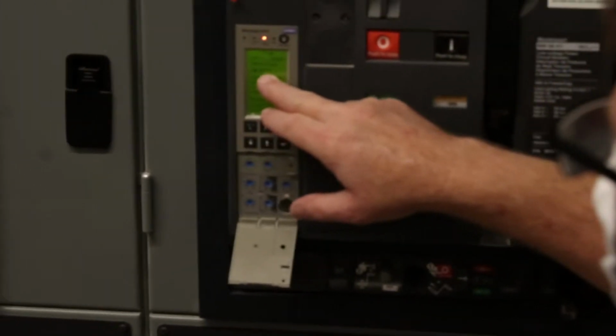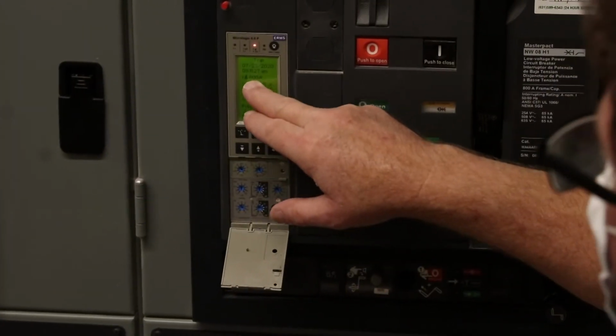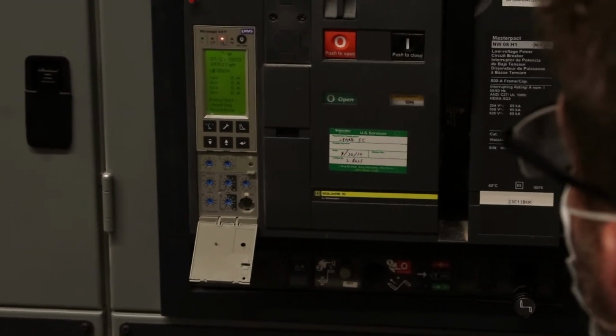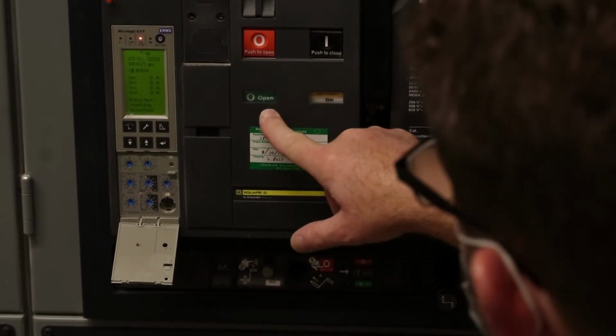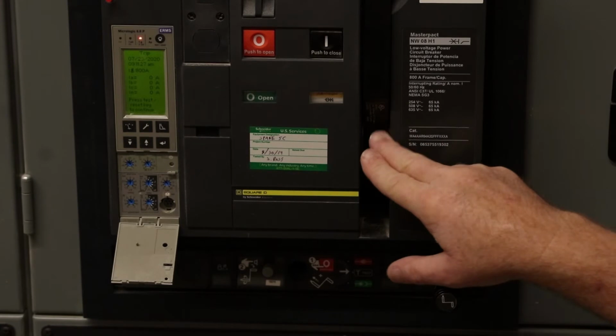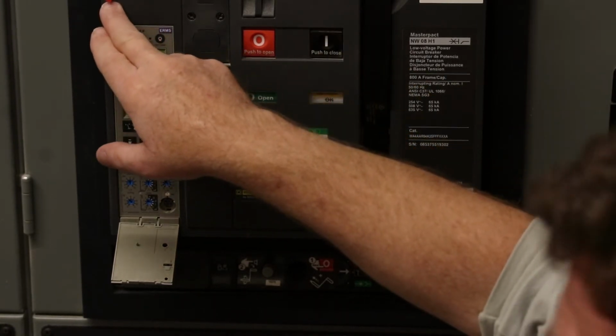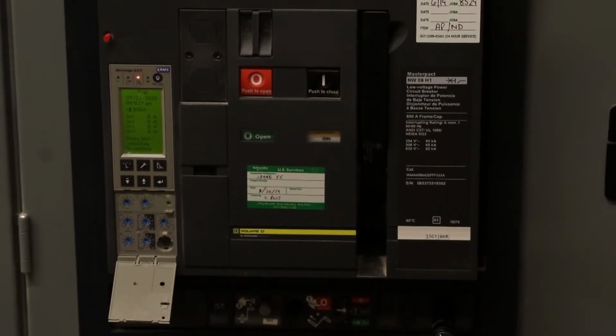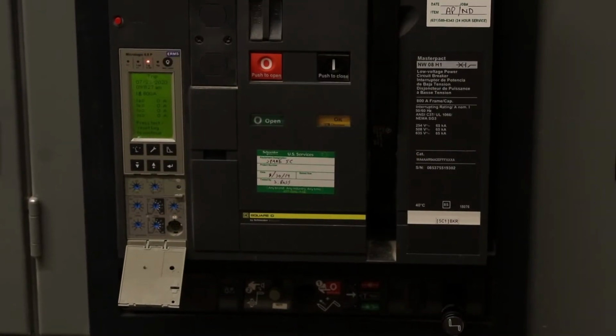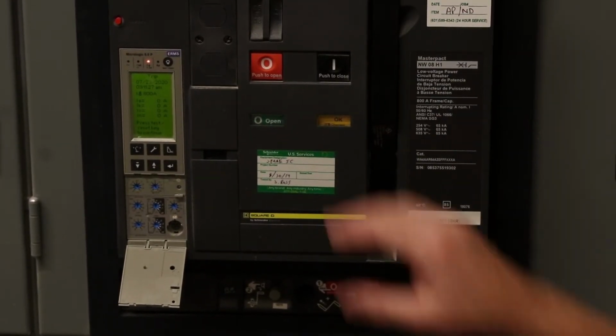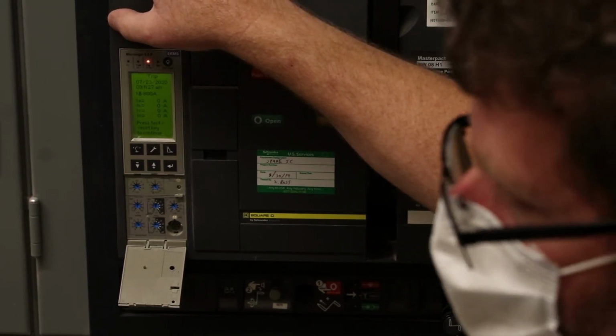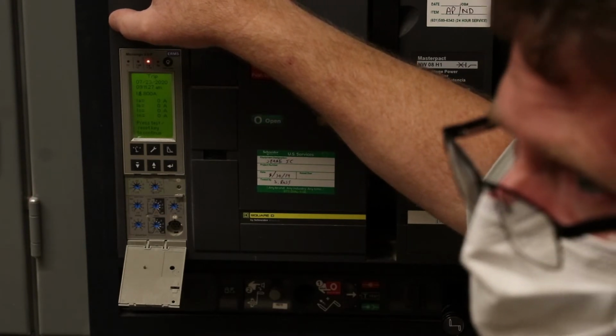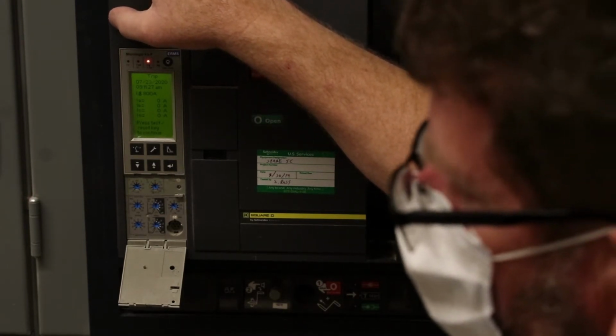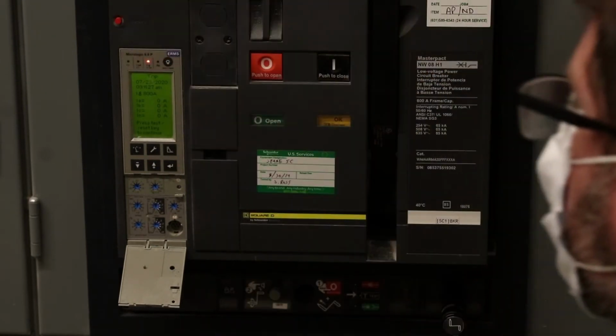Push the test on the ground fault, tripped off on ground fault. It shows you your date time stamp. It's not showing any phase current because there was no phase current. Simulated ground current was 800 amps. Okay, the breaker's open now, but it's still saying charge not okay. Saying charge not okay because it's not okay to close, because your red button's popped out. It's tripped. Resetting this doesn't mean the fault's cleared. Whatever tripped the breaker, that doesn't mean the fault's clear. That's just one step we put in the process to aid the operator to make him think, is this really safe to close back in? It means nothing as far as whether the cause of the fault was corrected.